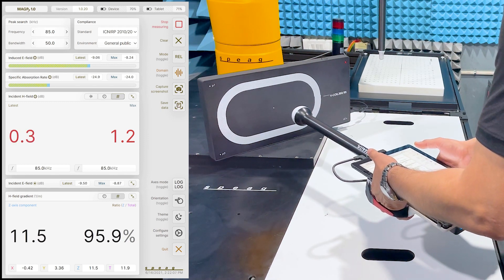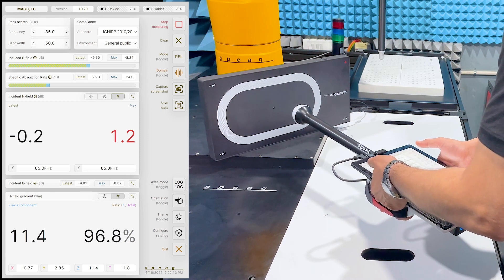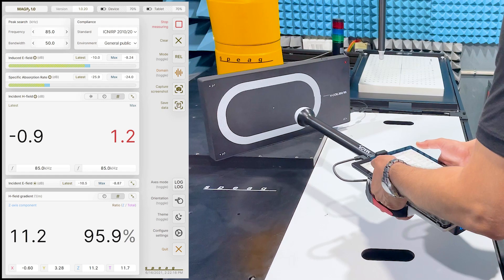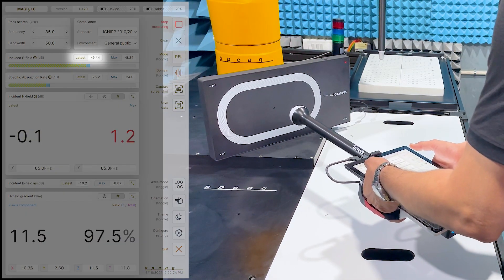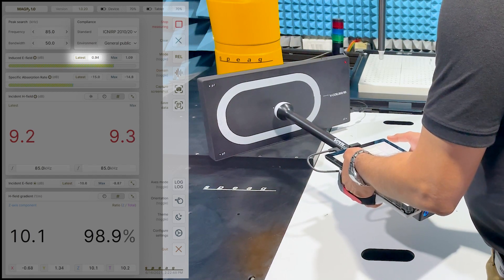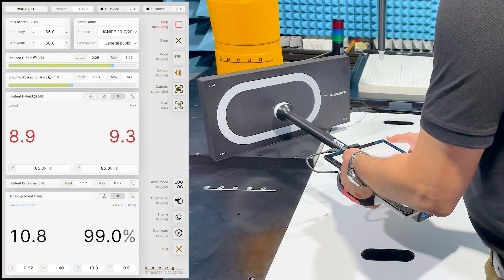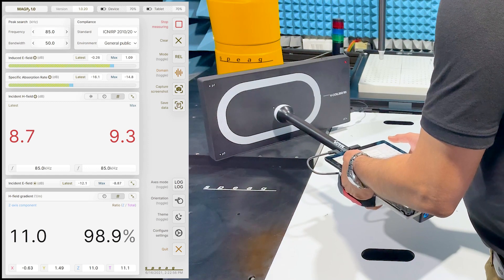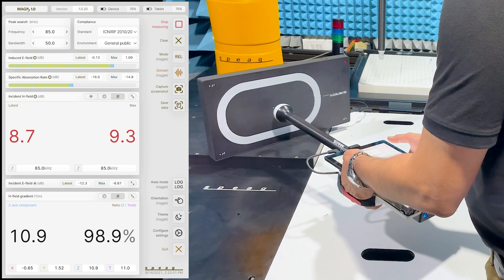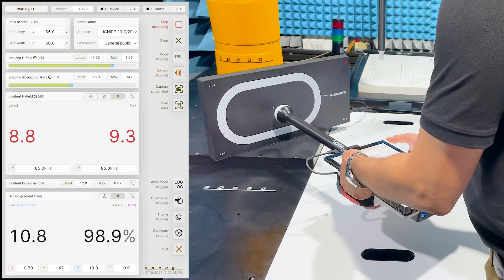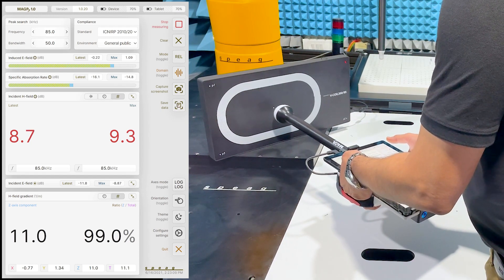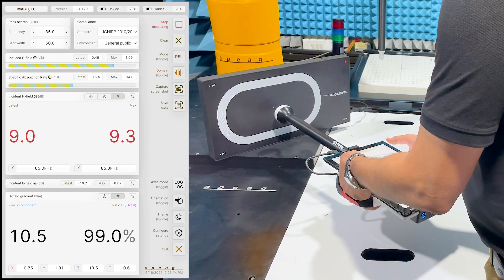However, the induced fields are still much lower. To find out the compliance boundary for the induced E field, I move the probe further towards the source and observe the current relative value of the induced electric field till it becomes 0 or positive. So, this point therefore corresponds to the compliance boundary for the induced quantities. This distance is approximately 2 cm from the tip of the probe to the source, even above the actual coil which is the location of the highest field level.